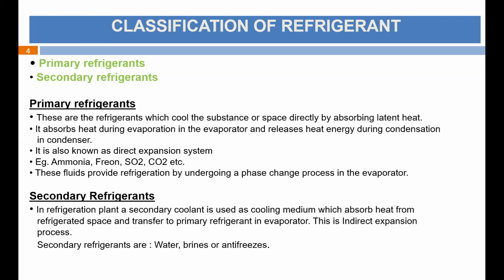Coming to secondary refrigerant, it is a refrigerant which absorbs the heat from the refrigerated space and transfers it to the primary refrigerant. Heat transfer between the primary refrigerant and secondary refrigerant happens in the evaporator. So this is called indirect expansion. You all know that in a chilled water system, water acts as a secondary refrigerant. That is in air conditioning, but in a refrigeration system where low temperature is required, we go for brine or antifreeze.